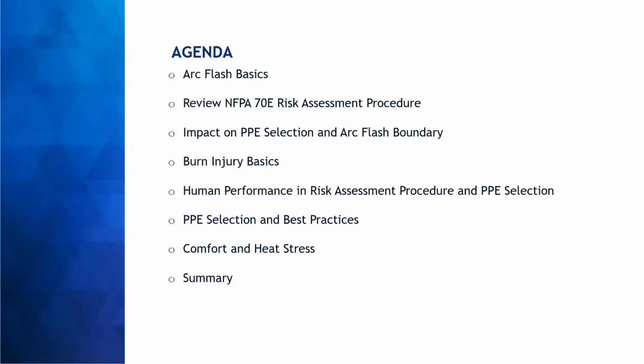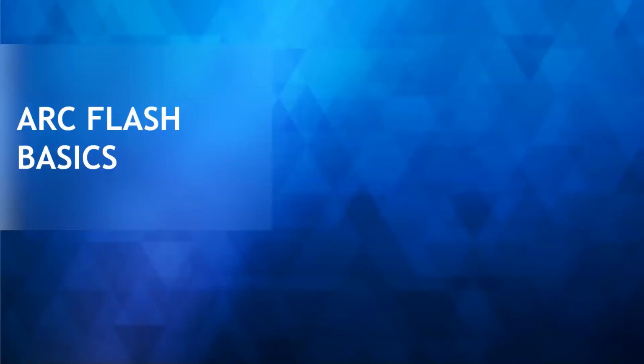And then finally, point number 3: if your organization has personnel that consistently works on energized equipment or consistently puts electrical equipment in an electrically safe work condition, which of course requires arc and shock PPE until it's proven that it's de-energized, then strongly consider a flame-resistant arc-rated daily wear clothing program. It serves as both a protective measure, because if it's worn, it will protect, as well as a preventative measure, and more on that later, that reduces the electrical arc flash injury and risk as low as reasonably practicable.